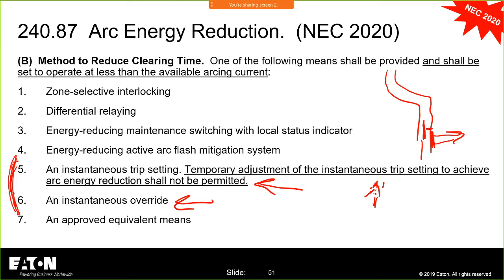And if it's not, if you're doing selective coordination and you're pushing these instantaneous values to the right further and further because you have to add intentional delays. We talked about selective coordination on Tuesday. If you're worried about not taking your entire plant down and you're adding intentional delays on the service entrance equipment, all the way up there at those big boys, the big devices, they're big because they can hold those contacts closed. We're going to learn that on Thursday of this week. Then you're probably going to need an arc reduction technology.